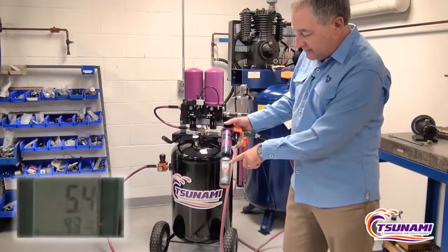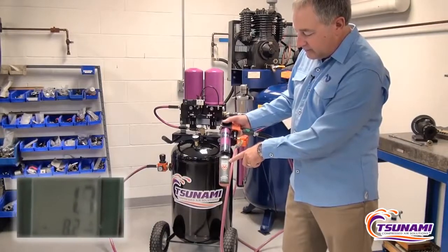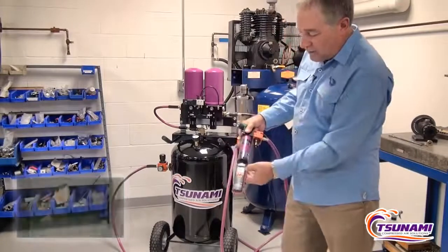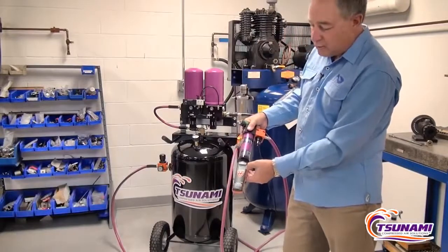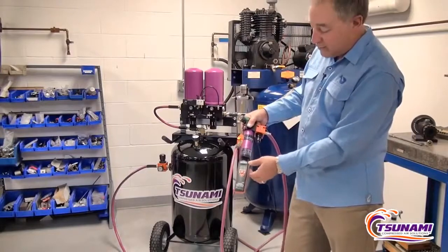And you can see we're dropping — we're at 13, 11, 10, 8, 7, 6%, 5%, 1%, 0.9%. Basically we're less than 1%. We're down to 0.5, 0.2. It'll go down to 0% relative humidity by running through the Rove, showing ultra-dry compressed air.